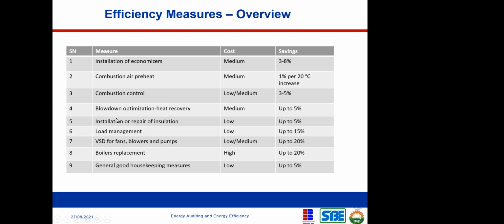What this one means, I have described what blow down means, right? So when you're doing your blow down, make sure that you recover the heat that is going out with the water from the blow down. Okay, so you need to recover that heat. So installation or repair of insulation. You know, the boiler system is a heat system. So if you don't insulate the walls of your boiler, you're going to lose more heat to radiation. So it is important that you insulate your boiler to make sure that you don't lose heat, because the whole essence of having a boiler is to transform water into steam, right? So we want to make sure that as much heat as possible goes into that process and not any other thing. Okay, so we need to insulate our boilers properly.